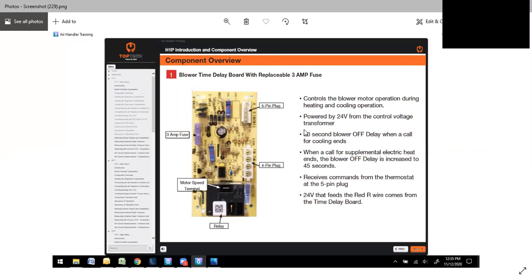The blower time delay board does contain a 3 amp fuse. One thing to be aware of: if you blow that fuse during installation, your fan will kick on and it will never shut off. It will just keep running and running when you have all your wires hooked up and your low voltage connections made.